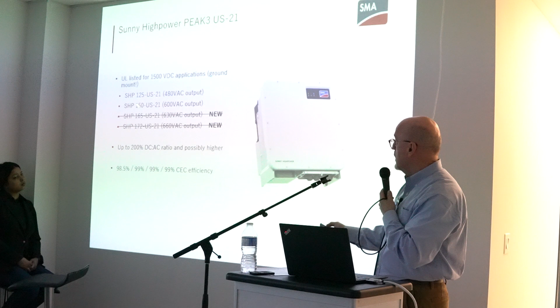As I mentioned in the intro, SMA is a leader in utility scale inverters. So we have a series of central inverters. Central inverters are built to order, custom designed for the specific application, really long lead times. It's a totally different animal. This allows you as installers to get involved in some large scale installations, ground mount installations. When we initially released this and started shipping it 2-3 years ago, we envisioned this maybe going up to maybe 10 megawatts range. We're seeing very, very large installations of this because there are some definite advantages of this architecture versus a central inverter. We have 2 power classes of this. We've got 125 kW and 150 kW.